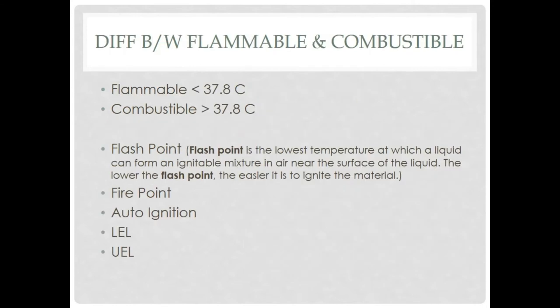First we need to know what flammable and combustible liquids are and how to categorize them. The difference between combustible and flammable is this: a flammable liquid has a flash point less than 37.8 degrees Celsius, while above that it is considered combustible. Now we need to know what the flash point is.